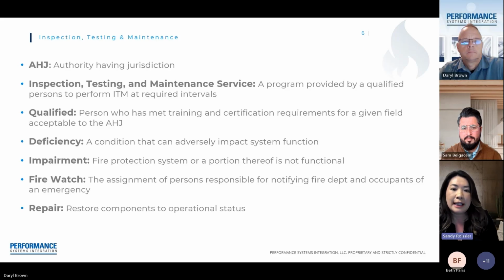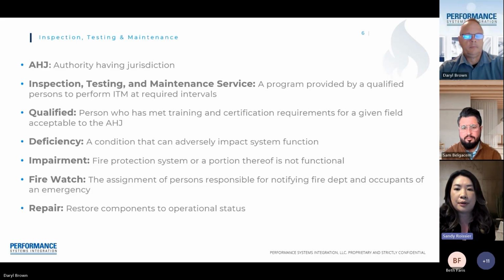Now, inspection, testing, and maintenance service. Inspection is generally a visual examination of the system's components and may require disassembly or operation of those components to verify the proper operation. Testing is the procedure used to determine the operational status of the components, and maintenance is the work performed to keep those systems operational. Now, these services are to be provided by a qualified person at the required intervals set by the fire codes. A qualified person is an individual who has met the training and certification requirements set by the NFPA and acceptable to the AHJ.